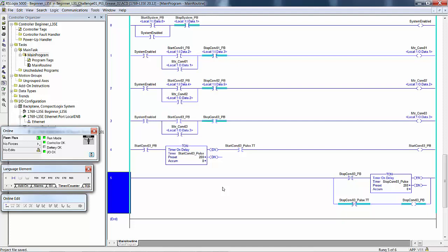And then every time I make changes and save it, I give it a different name. That way, if I want to go back to what the customer had at the end of the day, in other words, I didn't get all my changes made, I can always download what they had to begin with, and it's right back to where it was.